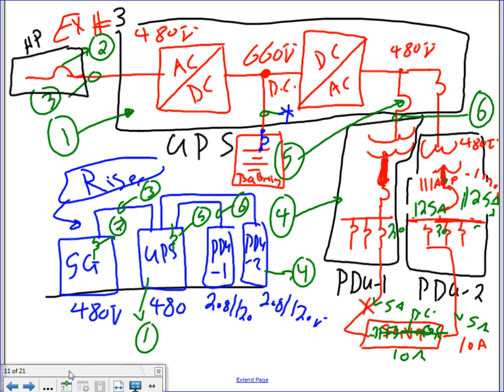Okay, so let's start from this one. Adam, you have a high voltage panel coming here, the switch gear, right here, can you see that? You're taking a feeder to feed the UPS system, which is the uninterruptible power supply and has a battery coming to it. What the UPS does is take AC and convert it to DC. They have converters. We're taking the AC at 480, converting it to DC, typically 660 volt, around 600 volt DC.